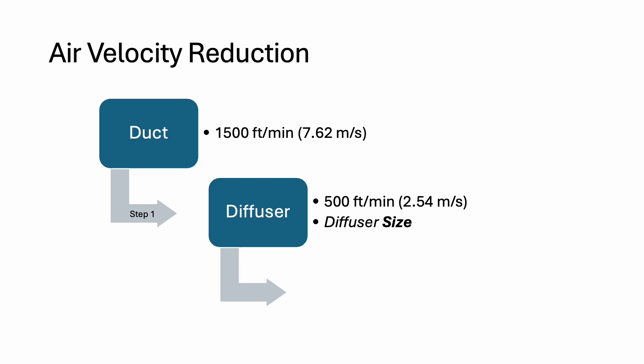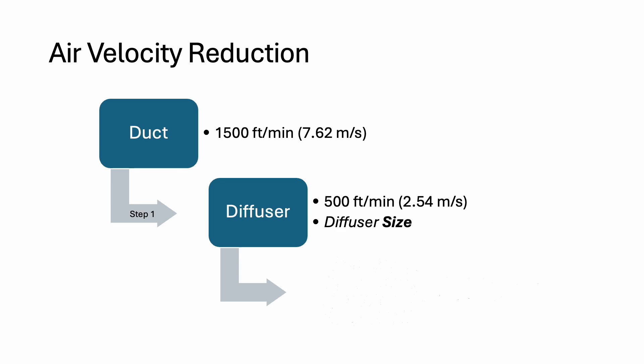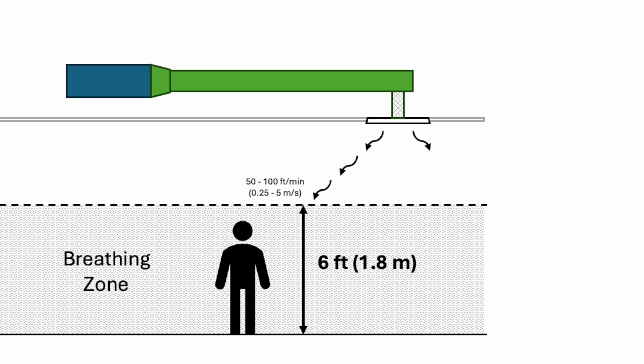As for the second step, the air velocity needs to be reduced from 500 feet per minute at the diffuser to 100 feet per minute before entering the breathing zone. The distance which the air travels from the diffuser to where it reaches 100 feet per minute is known as throw.